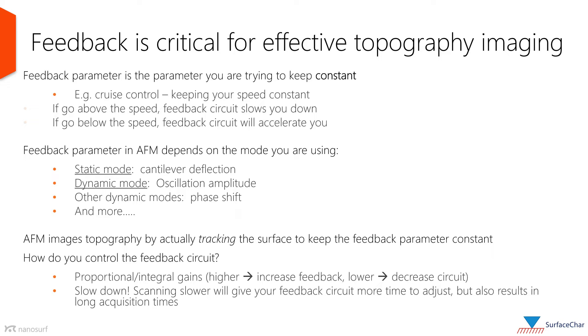In both modes, there is a feedback parameter set by the user, which the system attempts to keep constant. A good example is cruise control in a car, where the speed is kept constant by the car's computer, slowing it down if it goes above the set speed and speeding it up if it goes below. In static mode, the feedback parameter is cantilever deflection, and in dynamic mode, it is oscillation amplitude. Other dynamic modes exist with different feedback parameters, such as phase shift.